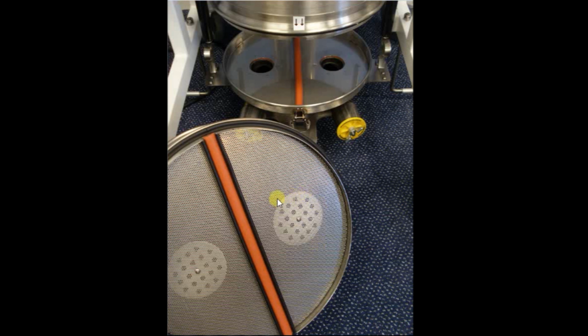Once the soda lime tray has been emptied and refilled, it's put back in with this seal in line with this one, and then pull these two leaf springs together, and the hydraulic ram will pull this soda lime tray and the absorber pan up tight against the bottom of the cylinder. Then fasten the two clasps at the back, refit the clasp at the front, and tighten those by pulling the clamps down and snapping them into place.